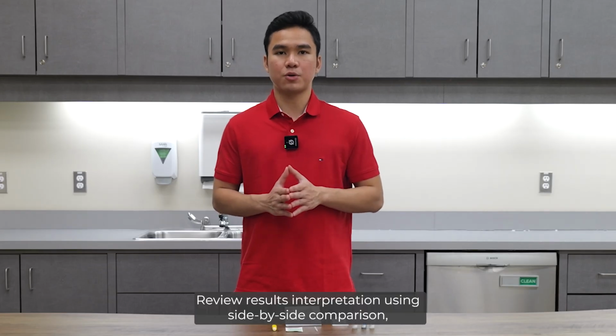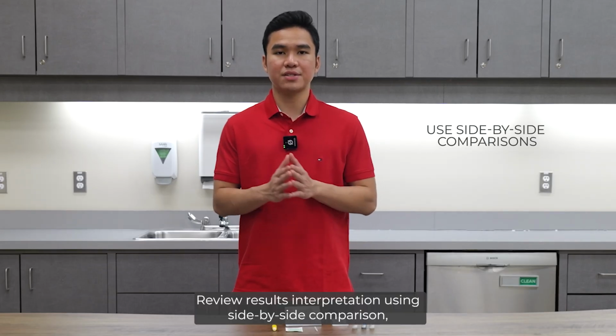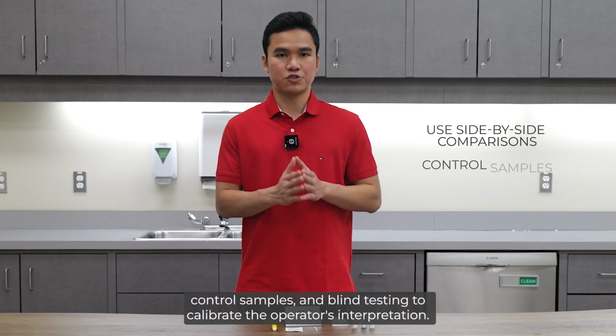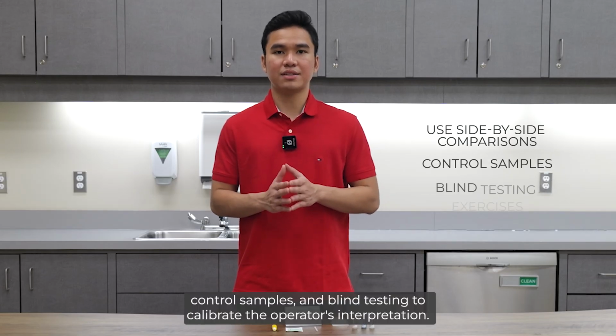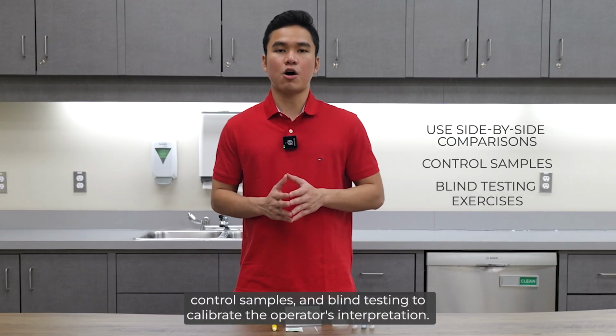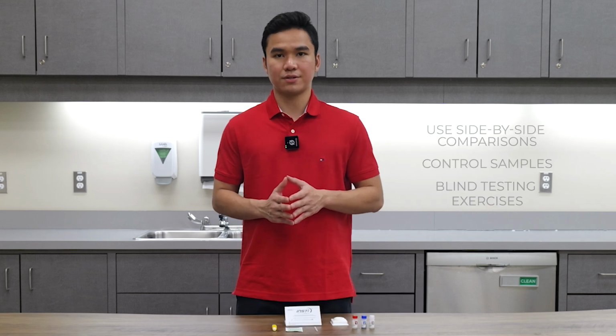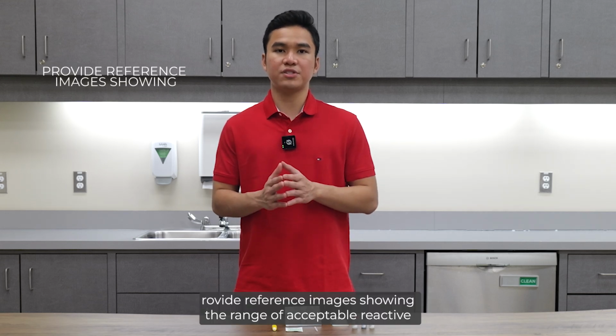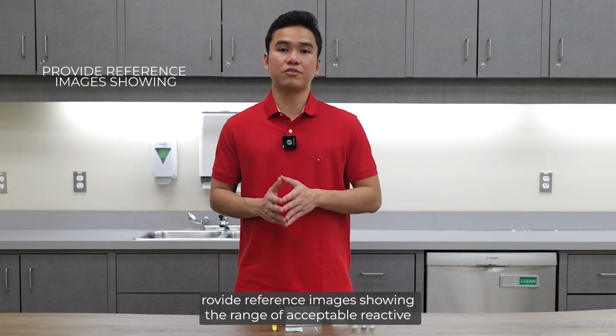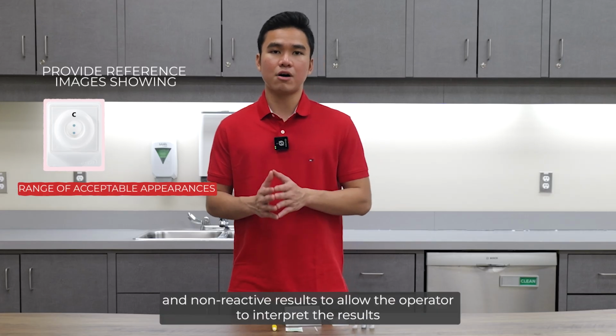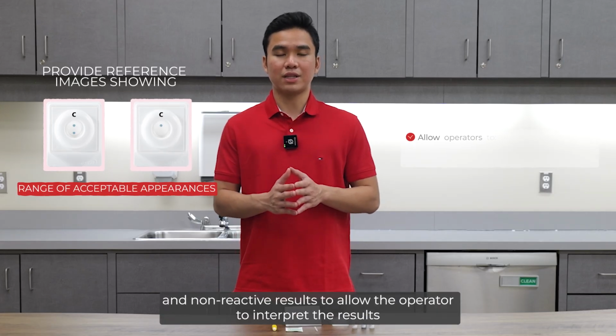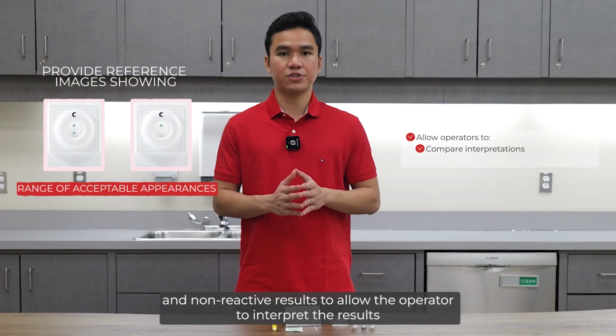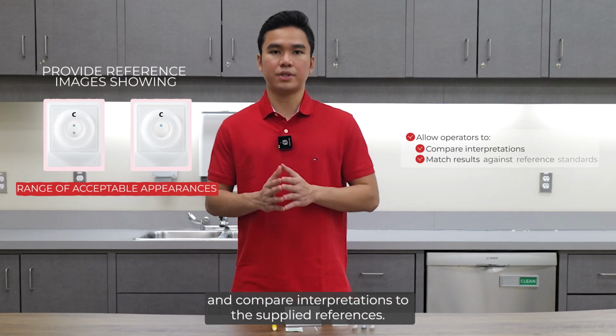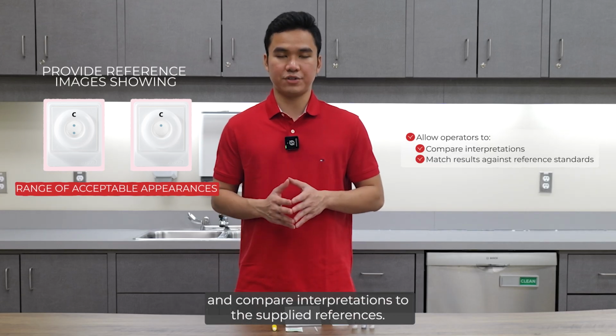Review results interpretation using side-by-side comparison, control samples, and blind testing to calibrate the operator's interpretation. Provide reference images showing the range of acceptable reactive and non-reactive results to allow the operator to interpret the results and compare interpretations to the supplied references.